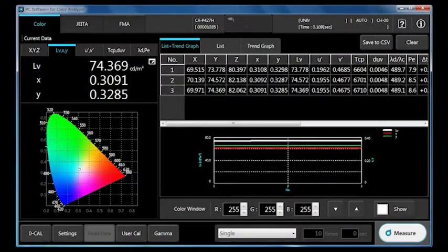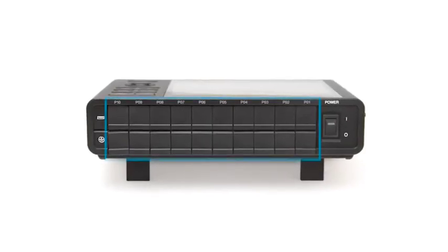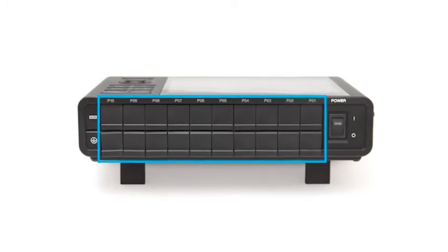The ability to conduct measurements faster and more accurately increases productivity, saving manufacturers time and money, while producing high-resolution displays by reducing the gamma correction process time. For example, the darkest level is measured in under 1 second, while brighter images are measured as fast as 25 to 70 times per second. The CA-410 has 10 available connection ports, which allows for multi-point measurements and increased accessibility.